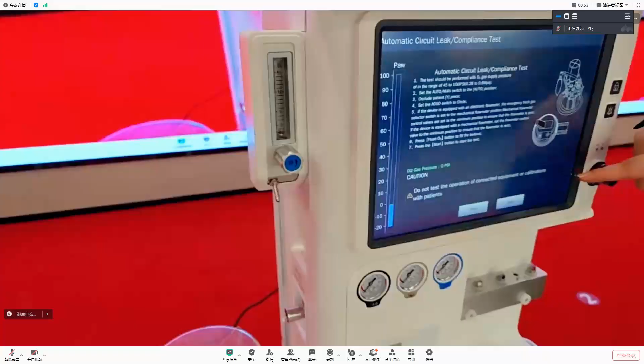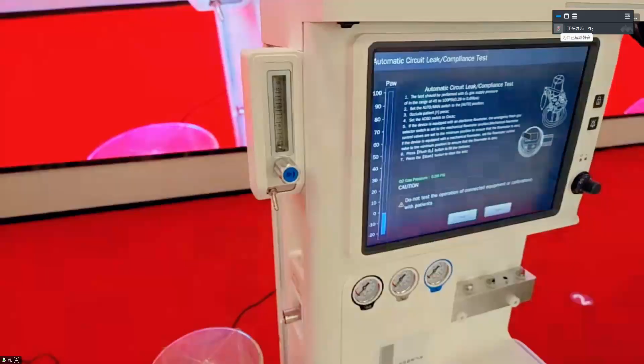Even for the basic model, we already have the real self-testing. For this self-testing, you can see after the checking, it's usually around 3 to 5 seconds. We are not using a long time, because for some kinds of emergency operation, we cannot wait. Some customers told us before about the testing time for the machine. We know some of the manufacturers use maybe 1 minute or something. But for our machine here, it's very easy. And as you can see, for different parts of the machine, we can check step by step. And after this, we can also automatically check the leakage. It's very important as well.